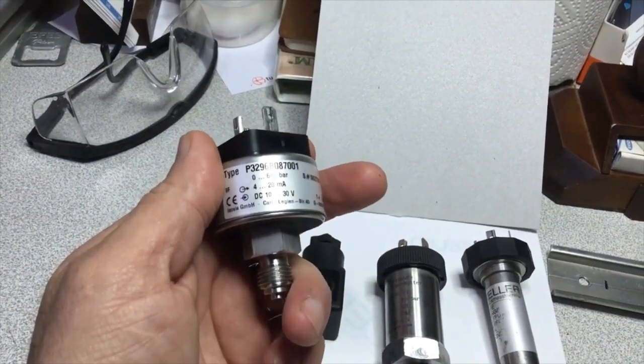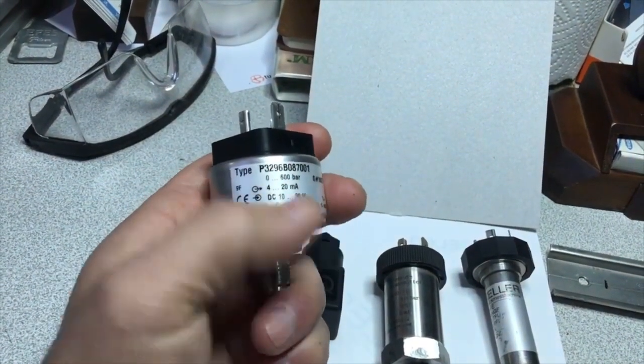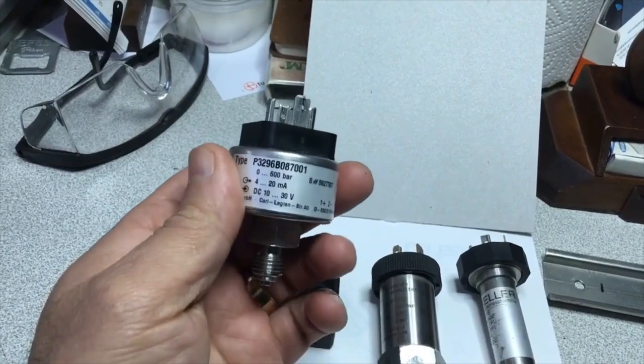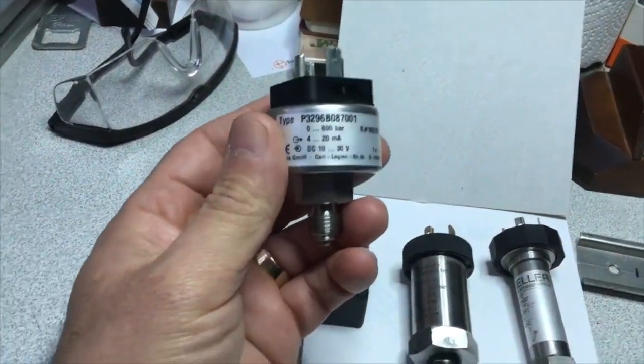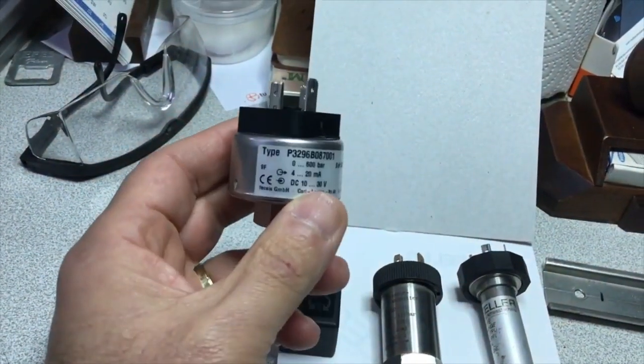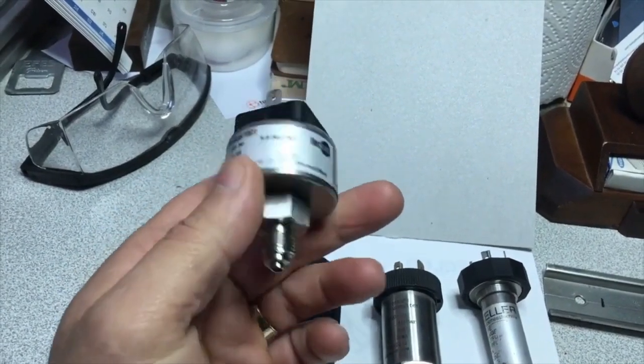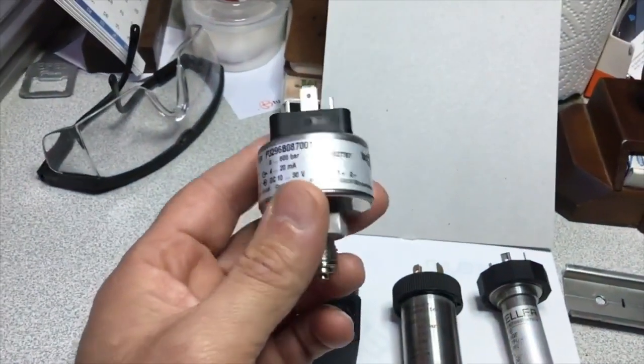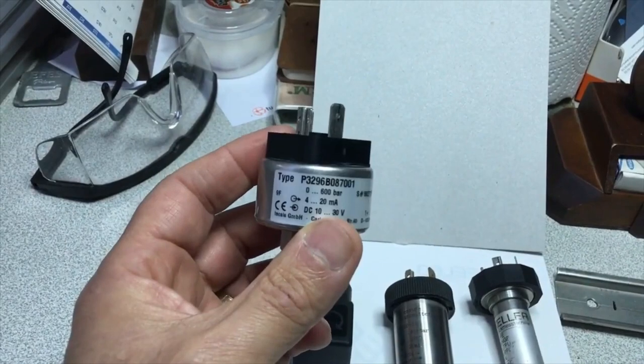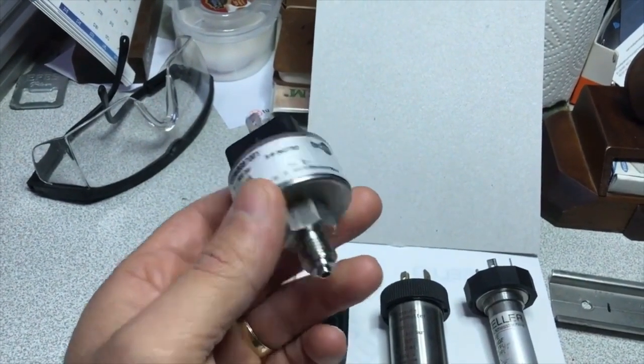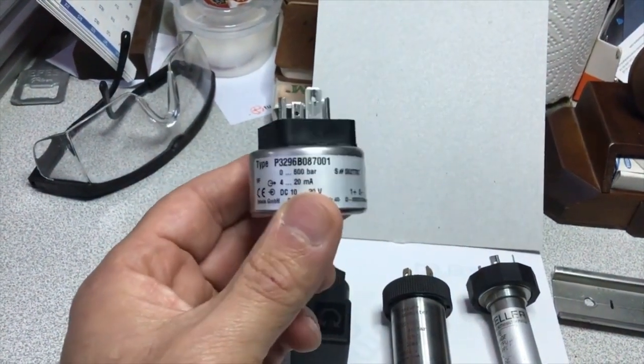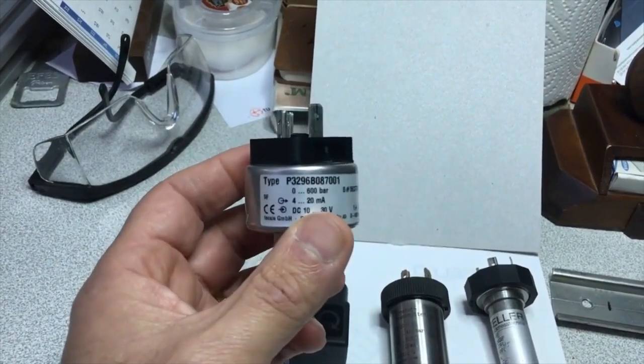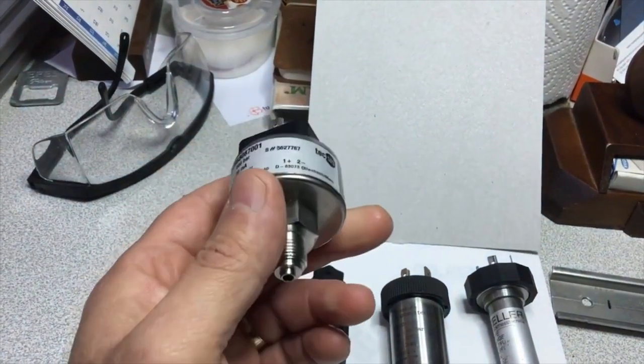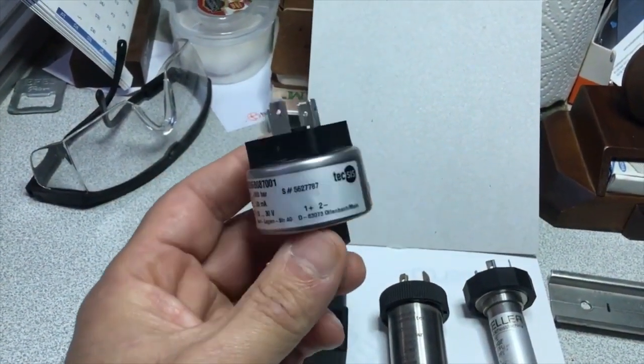Types that give 0 to 10 volts output make accurate measurements at close points, but when we want to carry them to long distances, we may read incorrect values because voltage drops will occur on the 0 to 10 volt cable. We also read the correct values with 4-20 milliamperes, that is, independent of the cable length, but when the cable breaks or the sensor fails and cannot output, the controller will take it as 0 bar system pressure, so we get wrong information.